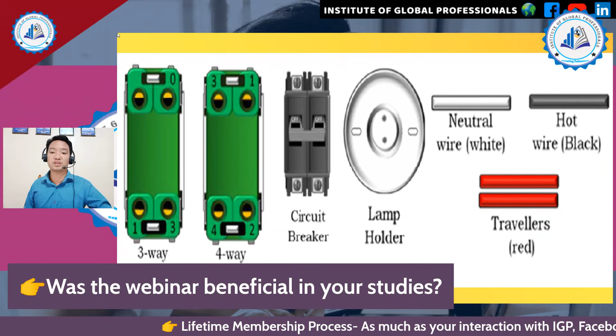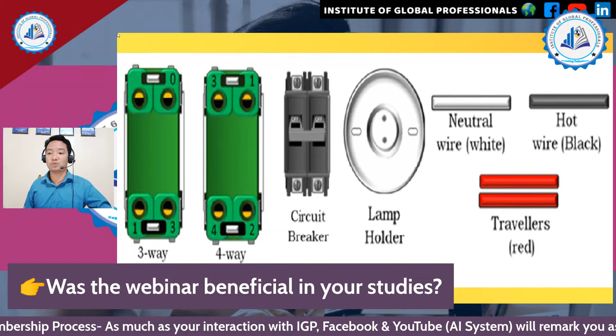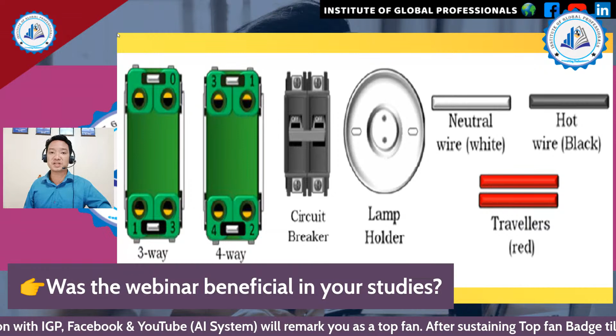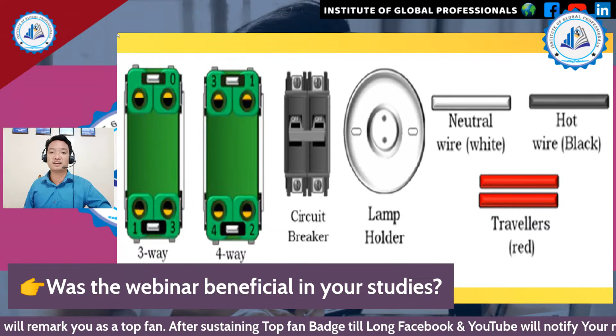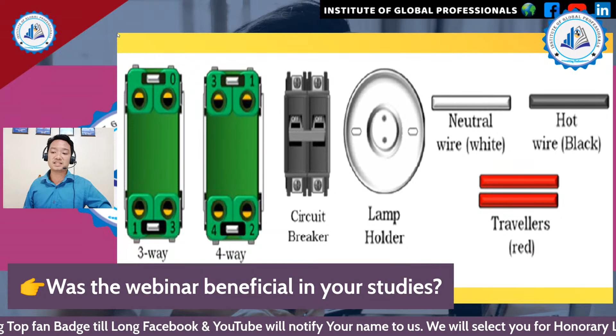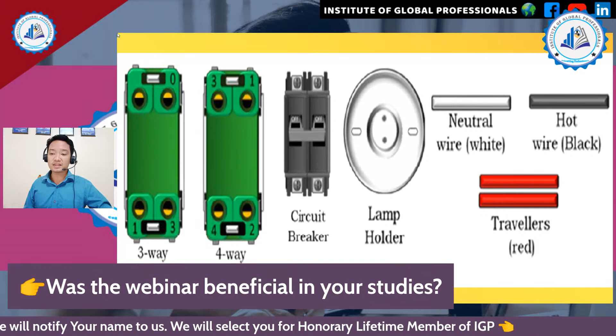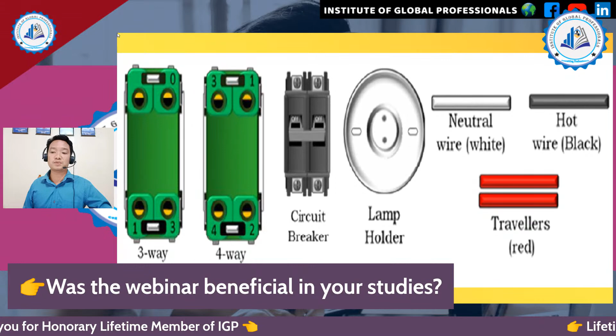We also have the lamp holders and the different types of wires to be used. These are color coded: white serves as the neutral wire, and the black wire serves as the hot wire. This is used from the circuit breaker to the switches, while the neutral wire is used from the circuit breaker to the bulbs, and also travelers, which are color coded red. So this is the proper way of noticing the different types of fixtures and wires to be installed in the wiring diagram.